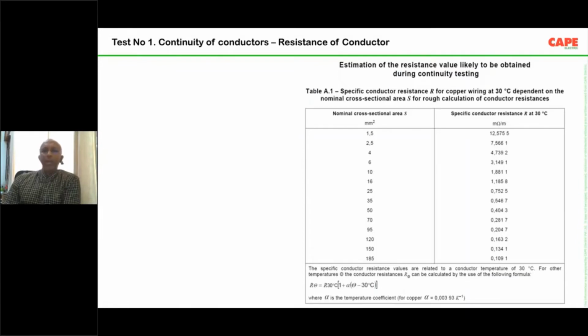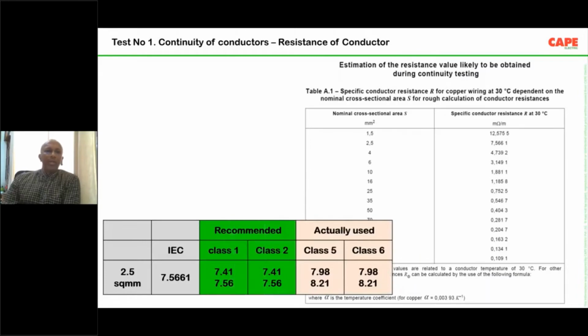I repeat, worldwide. This is the maximum allowed resistance of the conductor which has to be used for wiring. Now, in India, what happens? A 2.5 square mm wire, a classic case. In IEC, the recommended value, not only in IEC, this is what is followed across the globe, including Africa. IEC recommends 7.5661 ohm per meter. So the recommended value is, I put it in the green color.